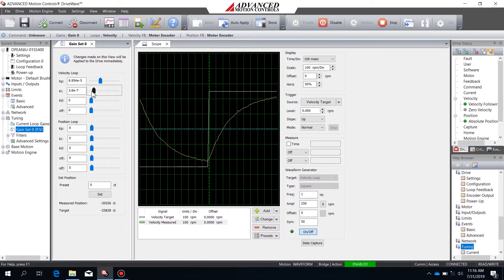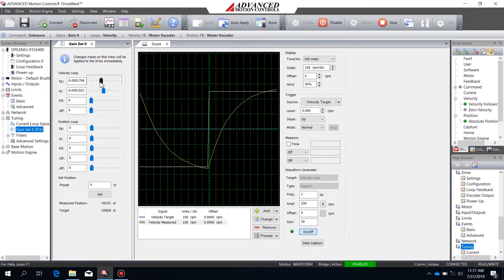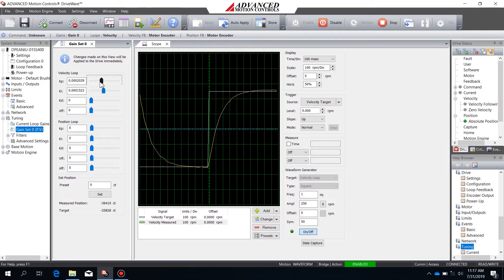As I increase the integral gain, I'm watching to make sure that when I hit the 250 RPM I stop increasing this gain. Once I've just exceeded the 250 RPM, I can go back to my proportional gain and continue to increase it to lower the rise time. You don't want the rise time too aggressive because that'll make the position loop harder to tune.